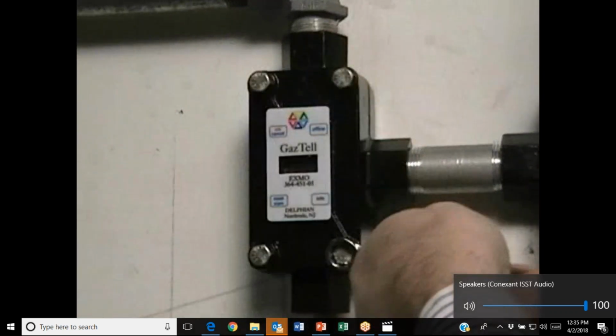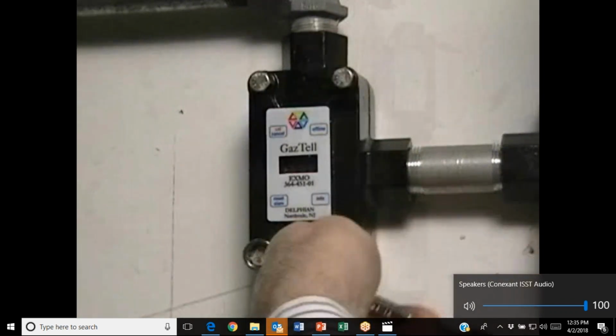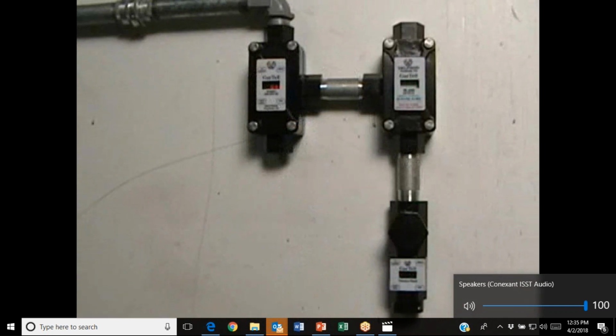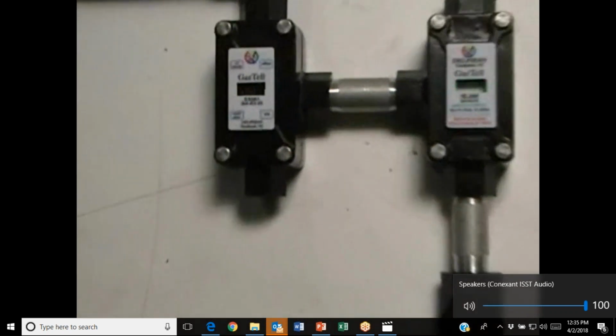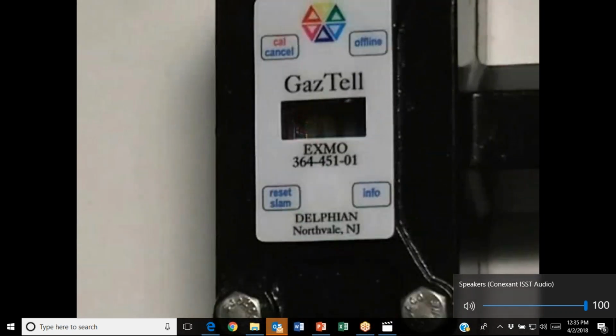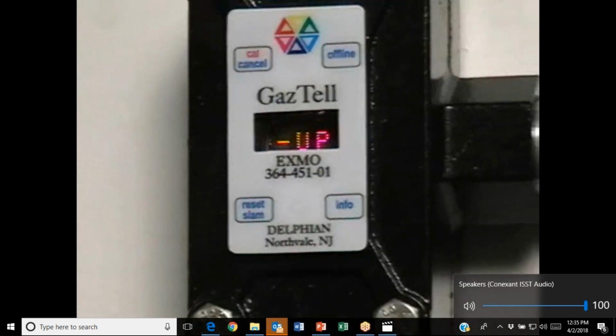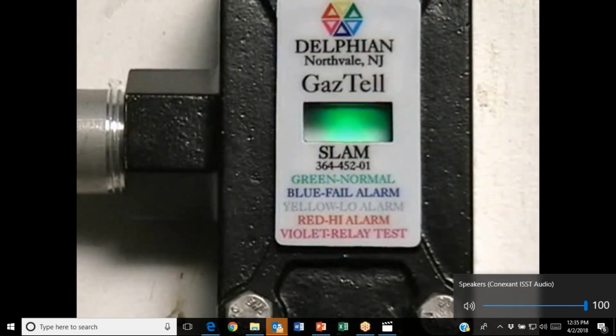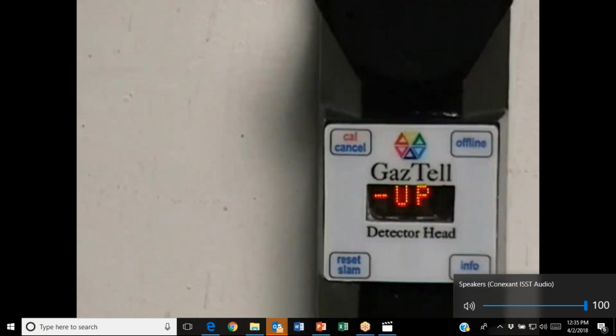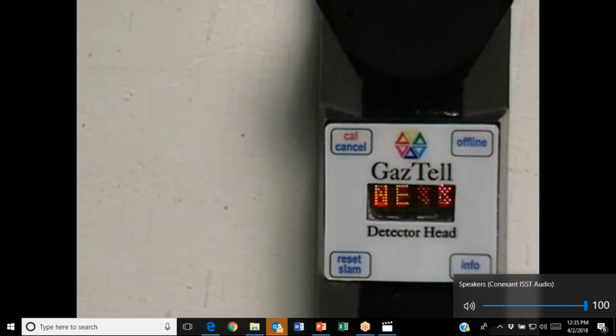Once completely closed up, you can supply power to the system to ensure your system has been installed properly. If 9 to 42 volts DC power is supplied, the detector and EXMO will display warm-up for approximately 40 seconds, while the SLAM, if it's installed, should be blinking green. This concludes the installation portion of the GazTell 450 video.